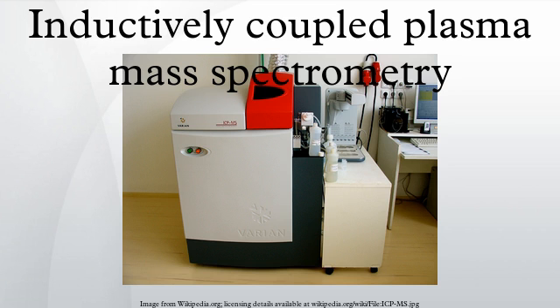Hardware. In terms of input and output, an ICP-MS instrument consumes prepared sample material and translates it into mass spectral data. The actual analytical procedure takes some time. After that time, the instrument can be switched to work on the next sample. A series of such sample measurements requires the instrument to have plasma ignited.